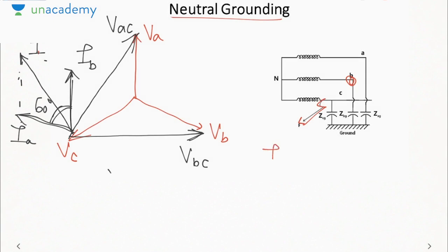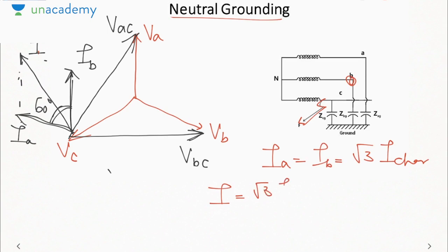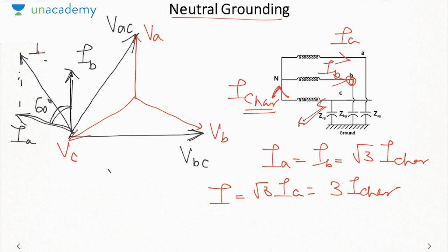Here IA is equal to IB is equal to root 3 times I charging, and the resultant I will be equal to root 3 IA, which is equal to 3 times I charging. So 3 times the line charging current will flow if the neutral is left ungrounded. How it will flow? It will flow in phase A and B, and it will come through the phase C. This I charging current is equal to IA and IB. So very high current will flow through the C phase winding if the neutral is left ungrounded.